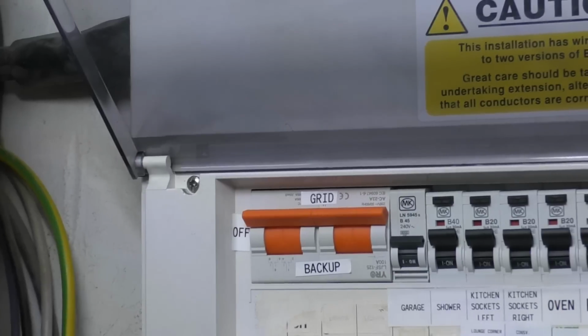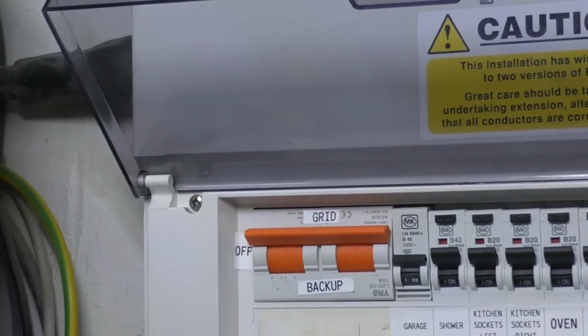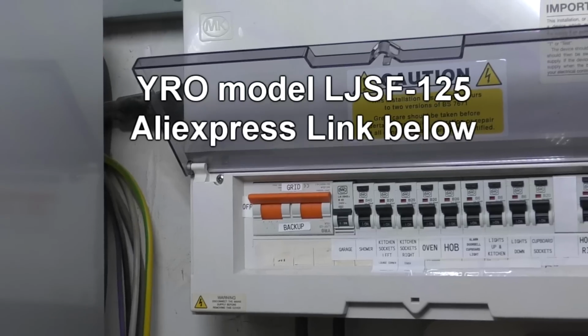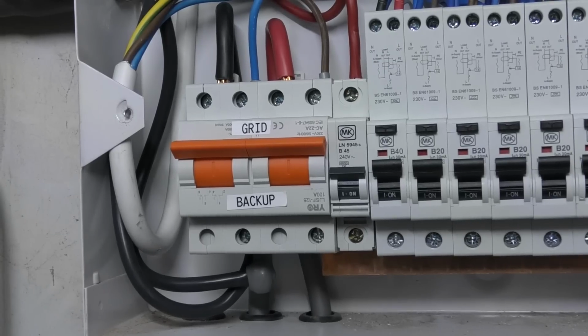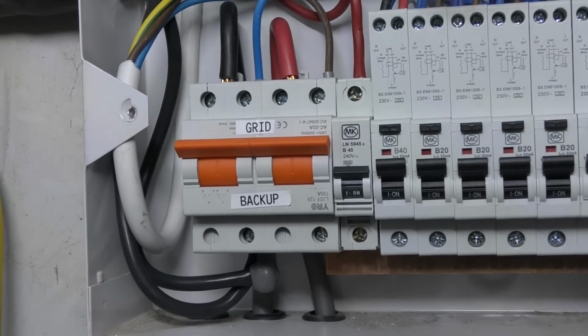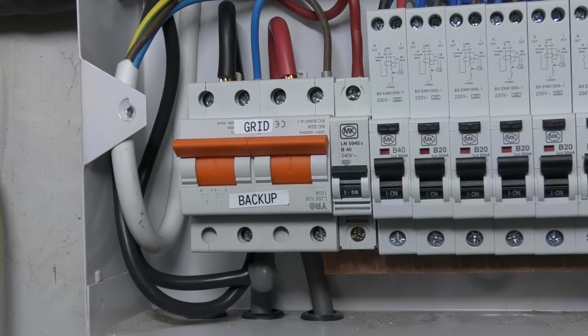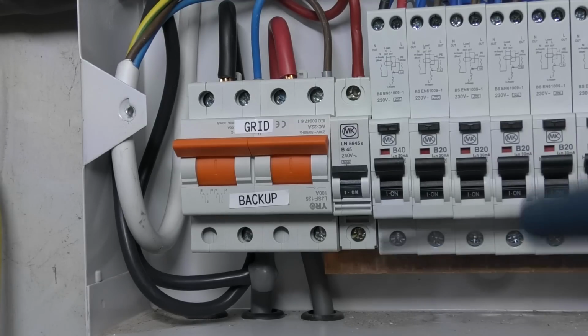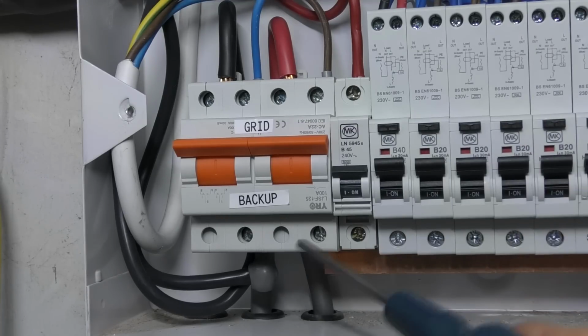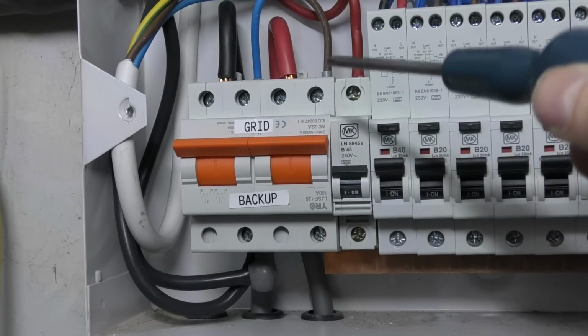So what I've done is I found this changeover switch. This was on AliExpress. This is a 100 amp changeover switch. I'll just pull the cover off this and show you some more detail. One nice thing about this switch compared to the other two I looked at is this actually has internal wiring for the changeover function. So we've got just 2 connections on one side and 4 connections on the other.